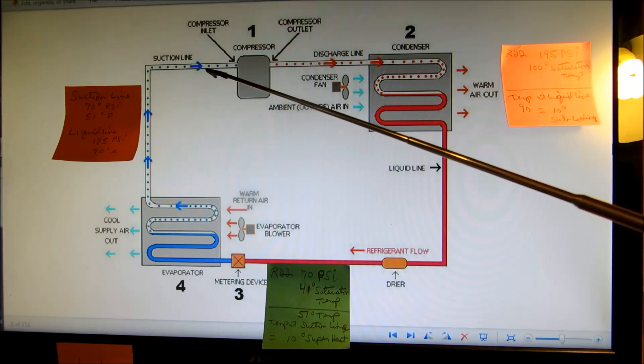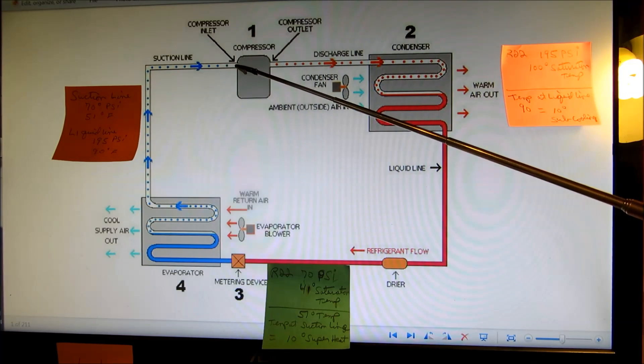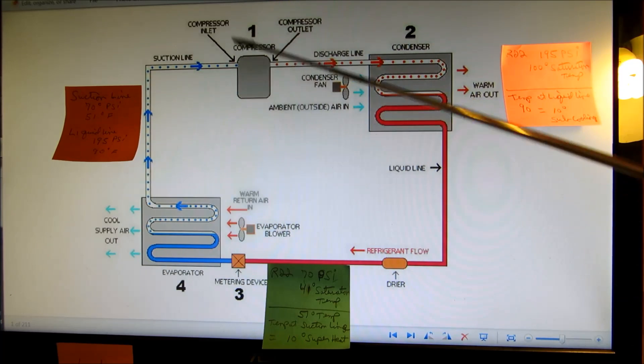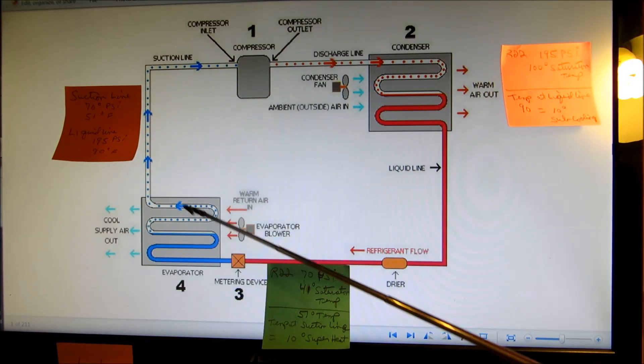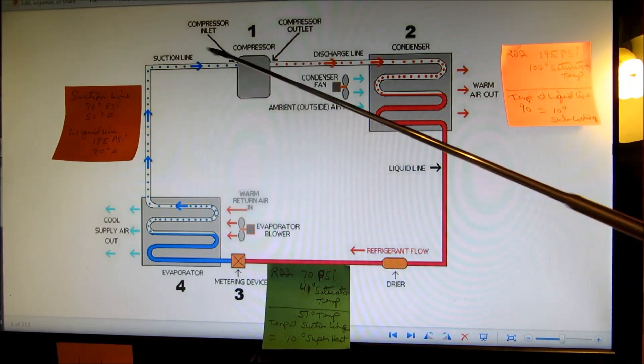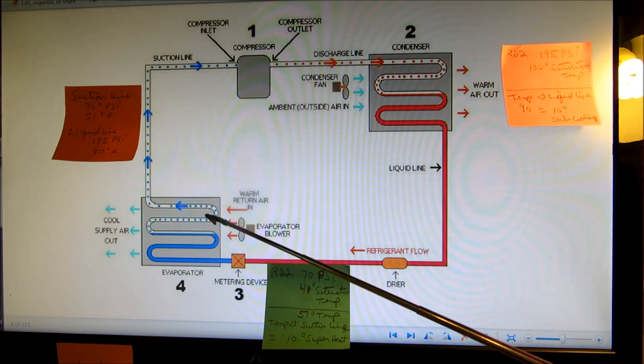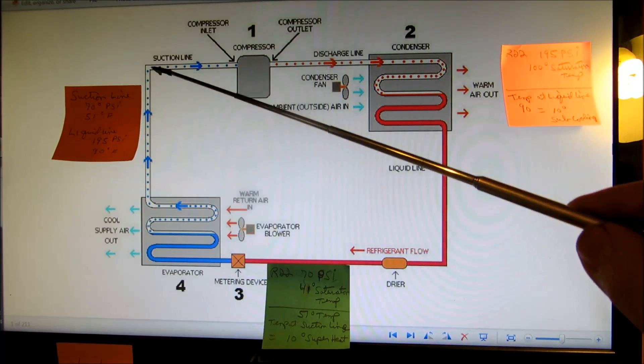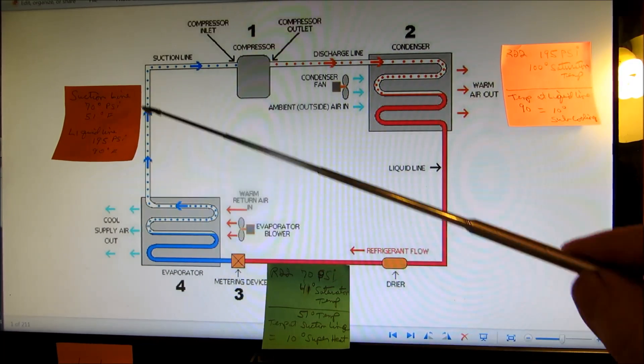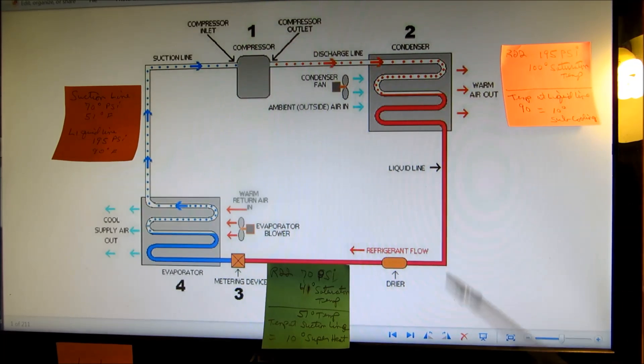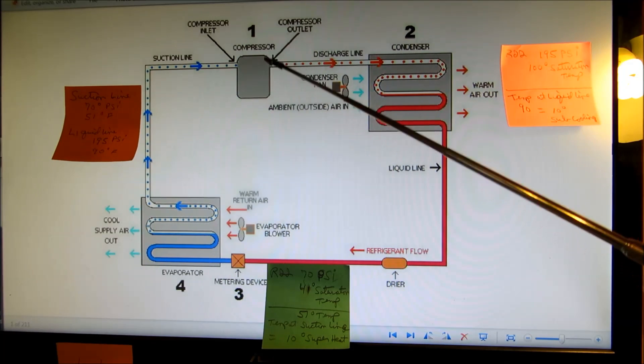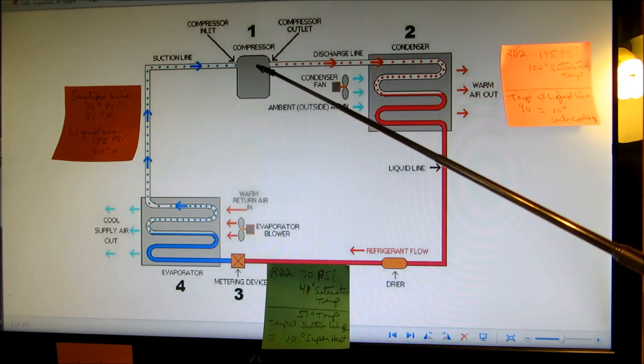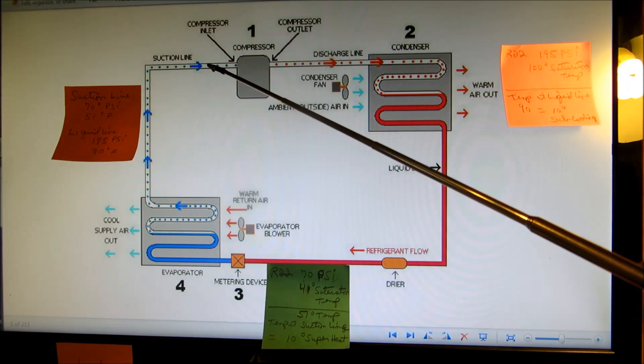So if saturation is 41 degrees and we're reading 51 degrees at the suction line, that's a 10-degree difference — that's what's called 10 degrees of superheat, or superheated vapor. The reason that's important is if you had zero superheat coming back to the compressor, you'd be pumping liquid to it and you'd kill it. The compressor is not designed to pump liquid — it's designed to pump superheated vapor.